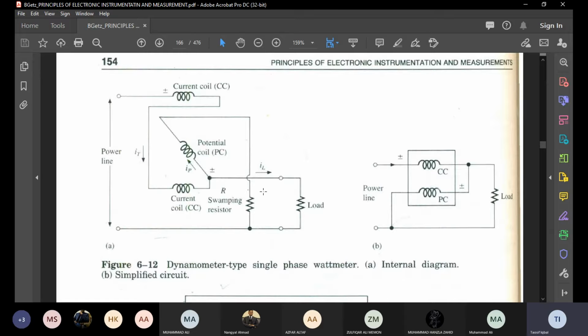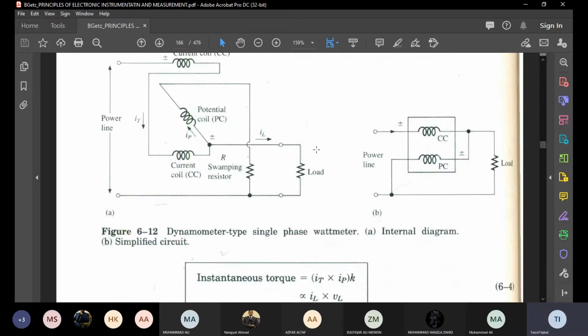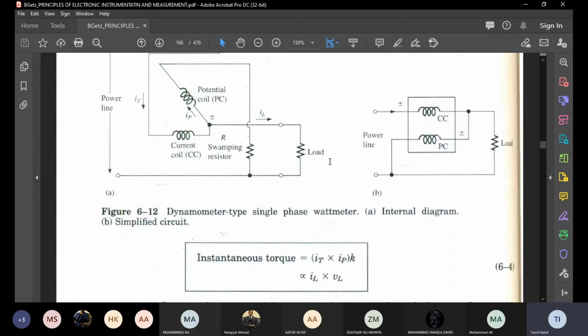So current coil and the potential coil, they are connected in such a way that first we have a current coil and then we have potential coil in parallel with the load, and both equivalent resistance they are in series with the potential coil. So in series with the moving coil there is a swamping resistance, and that is to mitigate the effect of heat produced by the current carrying coil of potential coil.